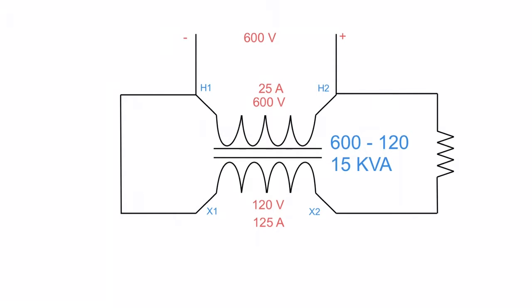From our earlier discussion on transformer ratings, whatever polarity H1 has, X1 will share the same polarity. So if H1 is negative, then X1 must also be negative; if H2 is positive, then X2 is positive. Now with polarity and ratings set up, we have positive 600 volts going into a negative 120 volts.